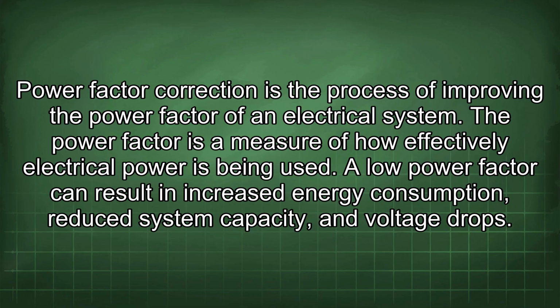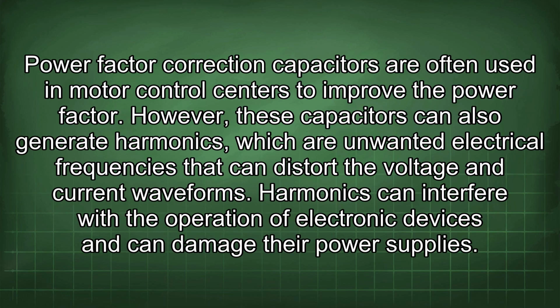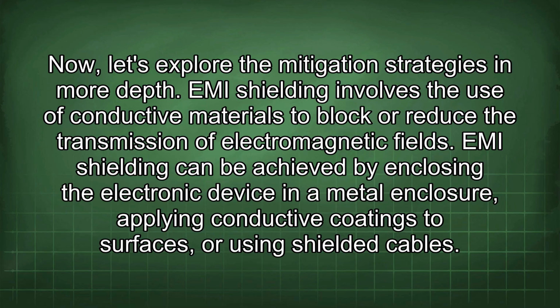Power factor correction is the process of improving the power factor of an electrical system. The power factor is a measure of how effectively electrical power is being used. A low power factor can result in increased energy consumption, reduced system capacity, and voltage drops. Power factor correction capacitors are often used in motor control centers to improve the power factor. However, these capacitors can also generate harmonics, which are unwanted electrical frequencies that can distort the voltage and current waveforms. Harmonics can interfere with the operation of electronic devices and can damage their power supplies. Now, let's explore the mitigation strategies in more depth.